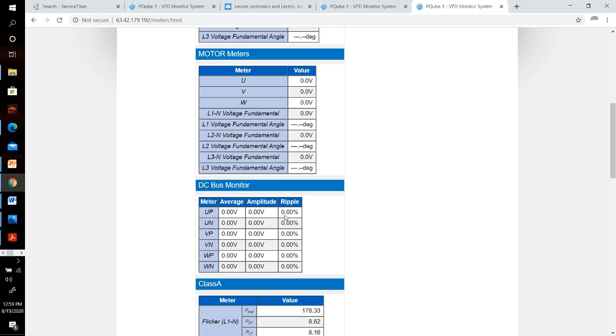So with all this information, I can put in limits on the drive scan to tell it, okay, when we hit these limits, I want you to send me a report or an alarm saying my capacitors are getting to a level where we need to consider replacing them. So we can predict a failure before it happens.